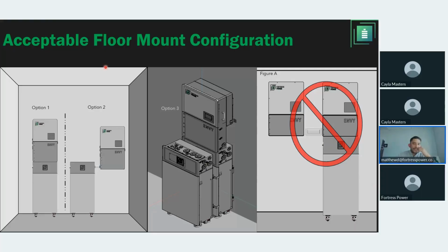What we don't accept is having one battery with two inverters, regardless of whether it's the 8K, 10K, 12K, or ENVY Duo. It's because you would be undersizing your battery system. You would be overloading current. Each 8K is about 167 amps charge and discharge. Then 10K is about 210 charge and discharge. And the ENVY Duo and the ENVY 12K would be 250 amps of charge and discharge on the battery side. So two of those, regardless of the size, would be undersizing your battery.